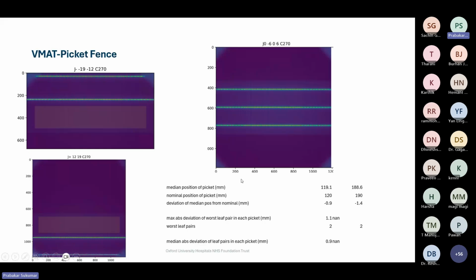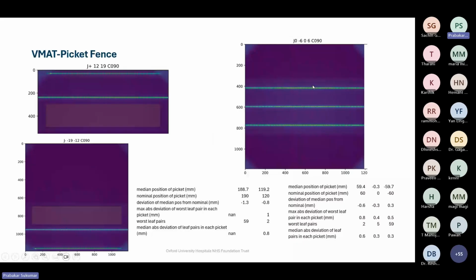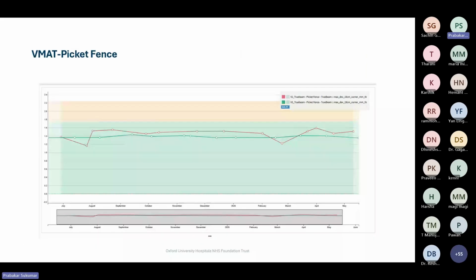What the script is running behind the scenes is this: it takes the profiles and uses the picket EPID image as a baseline, then measures the center of the EPID, and creates profiles along the lines of the MLCs based on the model that we give, and determines the positions of the peaks. At the bottom, it gives the worst deviations. This is done on one of the banks, and the next one is the other bank. You can see the same thing happening with the other bank, and the deviations we are getting are stored in the QA checklist. You can see the numbers generated from the scripts. It is a combination of scripts. There are a number of software packages nowadays which we can use to import the numbers into the QA checklist and use them as trends.